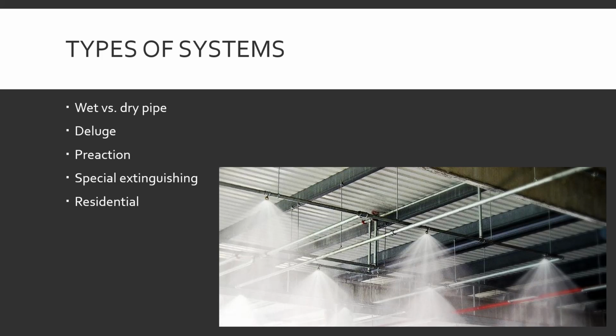Deluge system. Kind of already talked about it with the whole aircraft hangar. The system is open all the time. The alarm gets triggered. All the sprinkler heads are open. Water goes into the system. Water everywhere. Instead of this head that's broken and that one over there that's broken. This picture is a deluge system. Everything's open. Water goes in. Everything goes off.